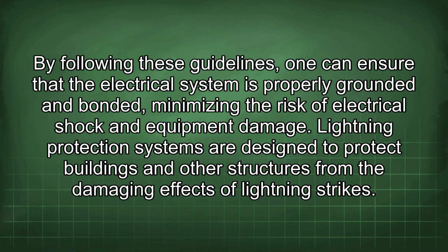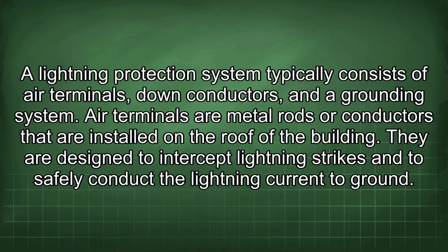Lightning protection systems are designed to protect buildings and other structures from the damaging effects of lightning strikes. A lightning protection system typically consists of air terminals, down conductors, and a grounding system. Air terminals are metal rods or conductors that are installed on the roof of the building. They are designed to intercept lightning strikes and to safely conduct a lightning current to ground.